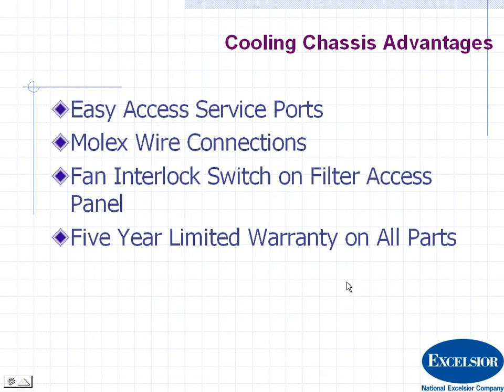A couple advantages with the cooling chassis: easy access service ports. Service ports are accessible by the front. You don't need to go around the side. Molex wire connections. They are not spade connections like some people have. So it's a Molex connection that snaps out, all the wires snap out. So if you want to pull out the chassis, everything's accessible to you. A fan interlock switch on the filter access panel, obviously for safety reasons. And a 5-year limited warranty on the parts.